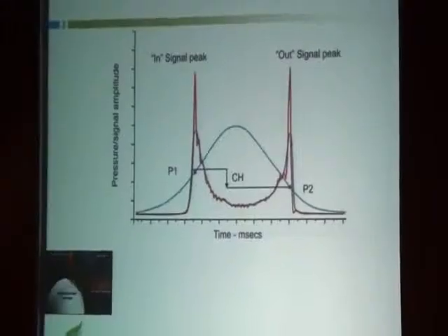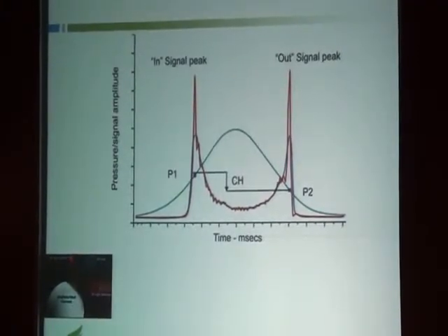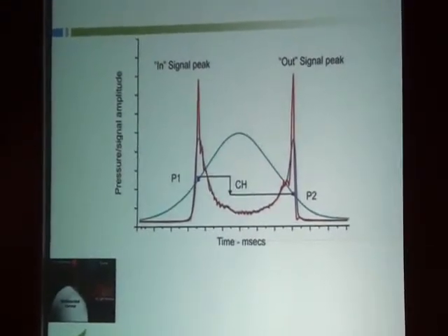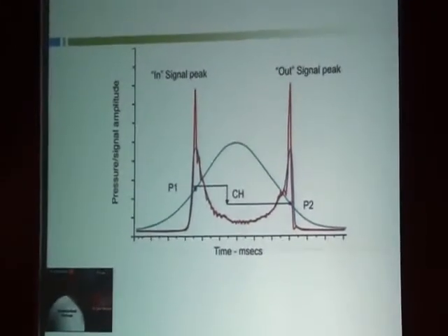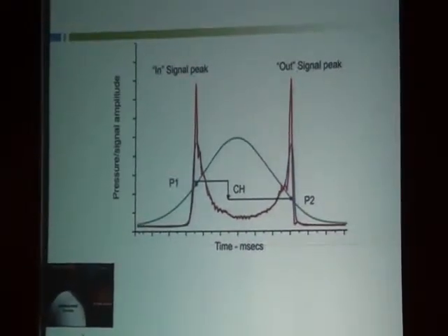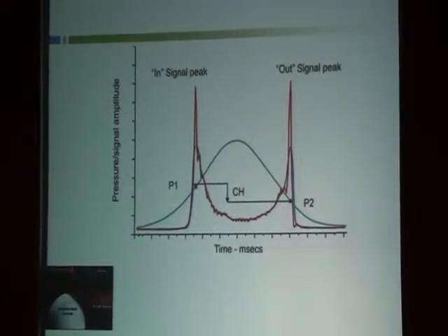Now, if we look at the way it works, it's a bidirectional dynamic process which is similar to a non-contact tonometer in the sense that the air pulse hits the cornea and deforms it to a point where it reaches applanation. In non-contact tonometry, at this point the process stops. However, in the ocular response analyzer, the process continues, and the air pulse continues to be delivered to the cornea beyond this first applanation. So with that, the cornea moves further.